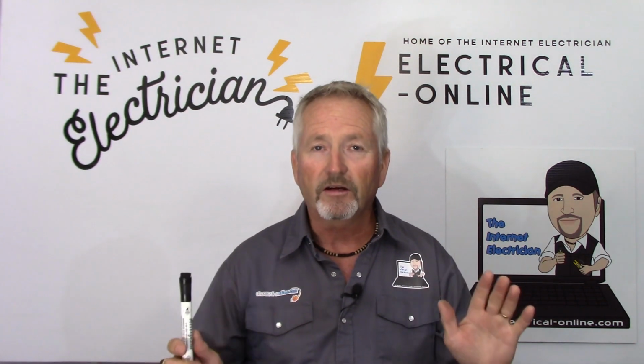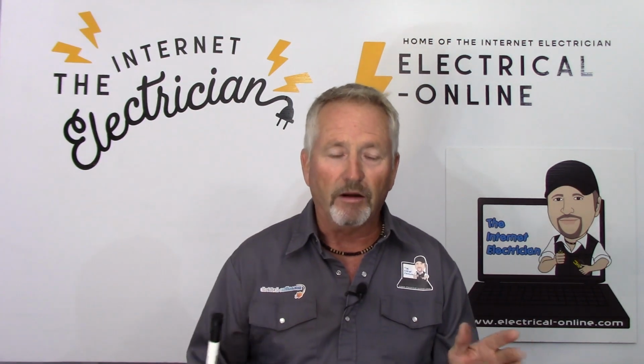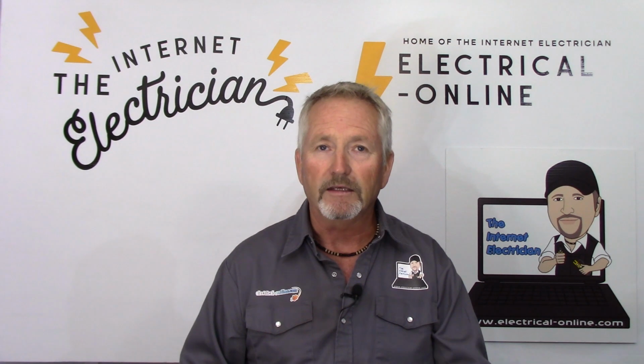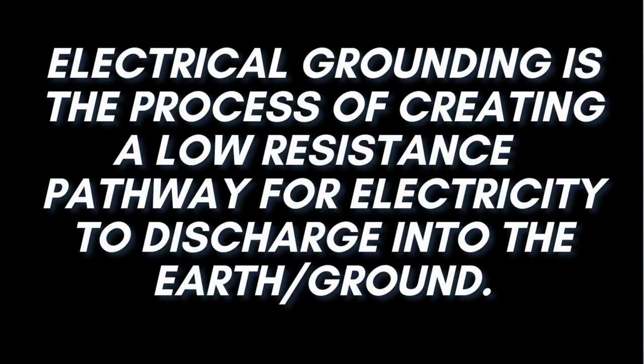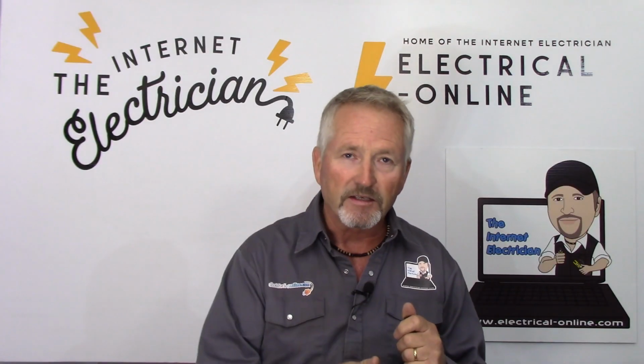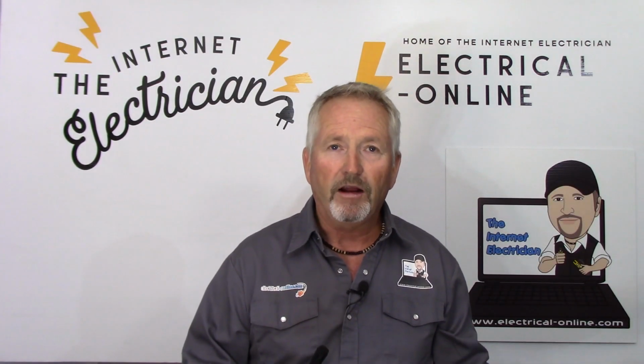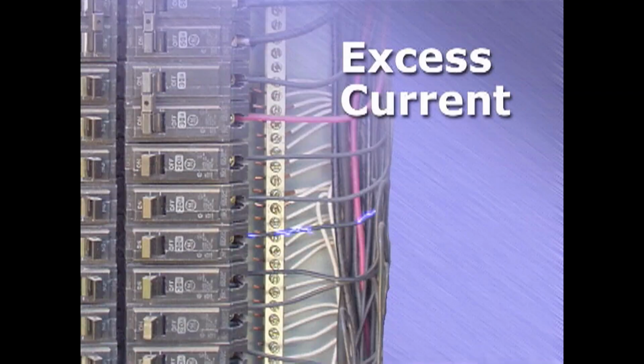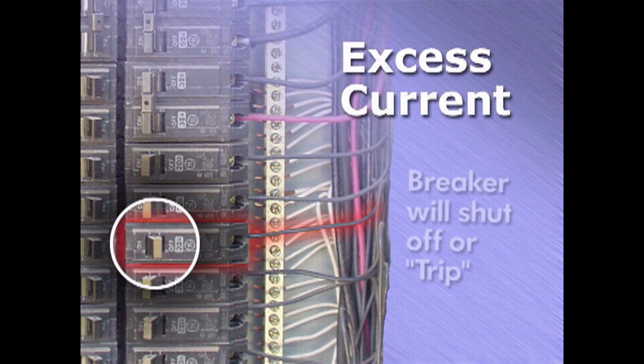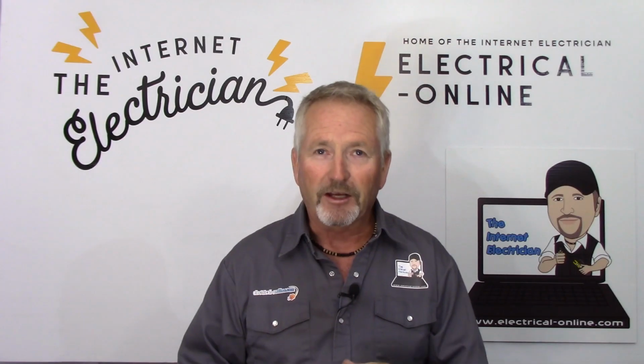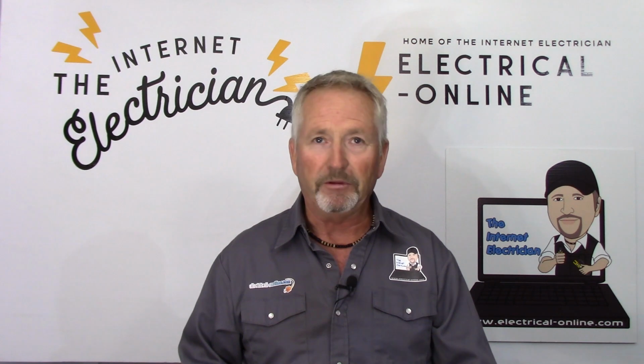So here's what the ground prong does for you. Grounds the circuit. Any metal parts of any device should be grounded. And if you don't have a three-prong cord like this, that's going to damage or take away that function of that ground. So what the ground does is, in a fault situation, it's designed to take all the current necessary to ground, safely to ground, and trip the breaker, because the breaker is set with fault trip current, that when it's a short circuit like that to ground, a whole bunch of current's gonna flow through that breaker and trip it, take away the power. That's a brief explanation. It's a lot more complicated than that, but that's the basics of it.